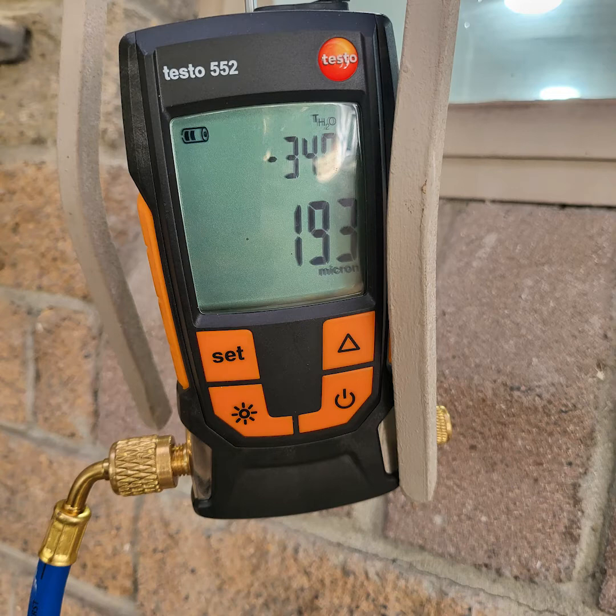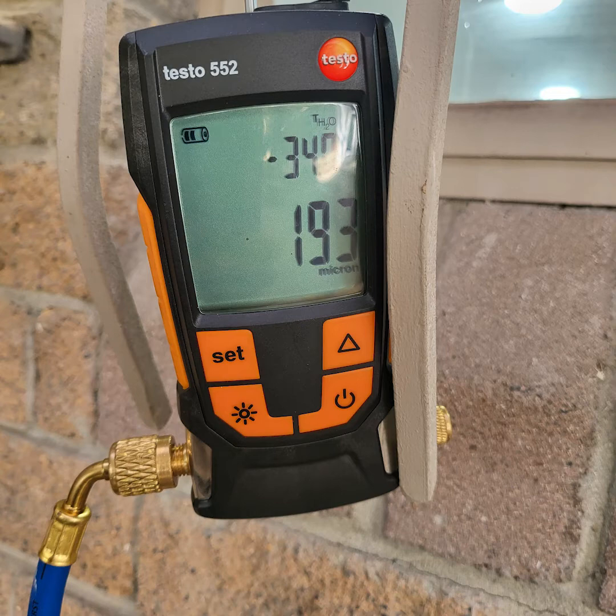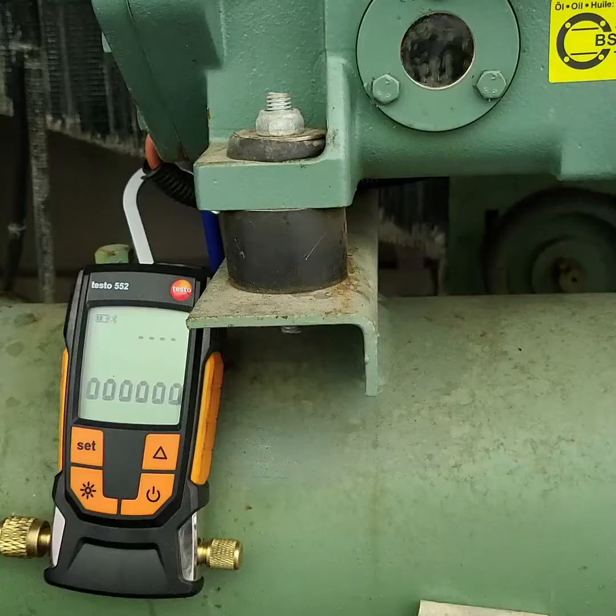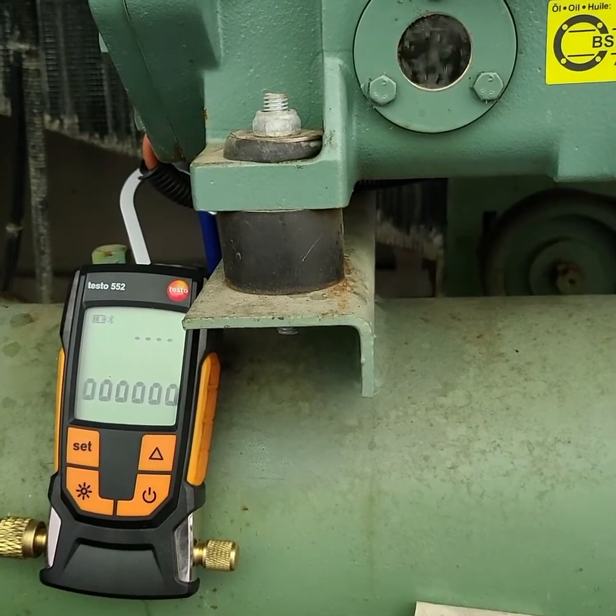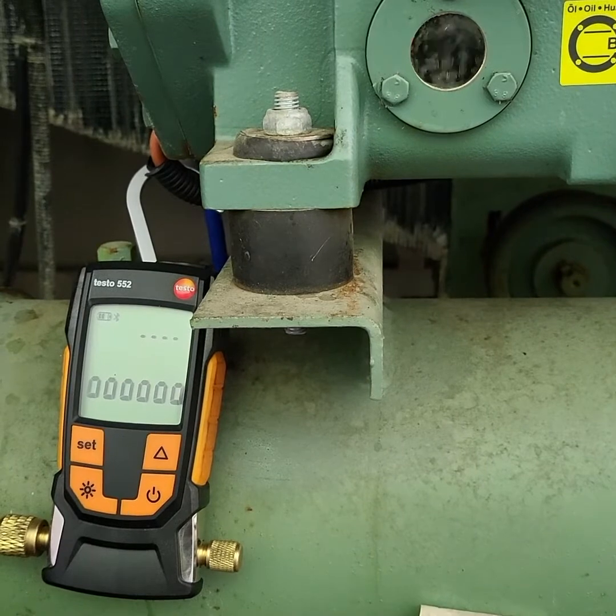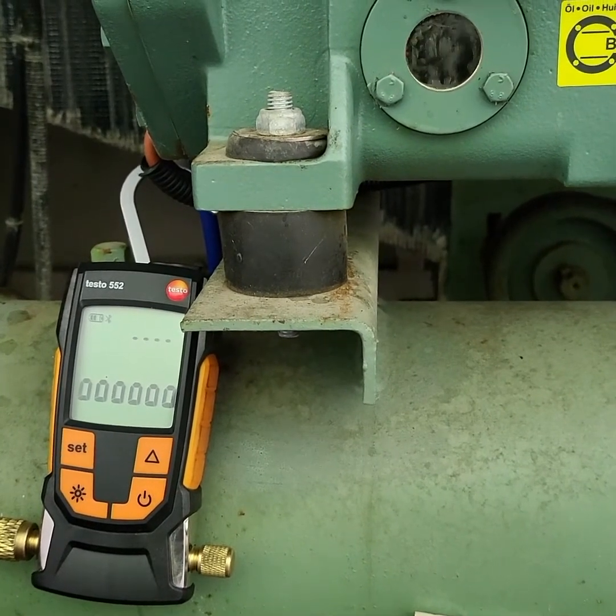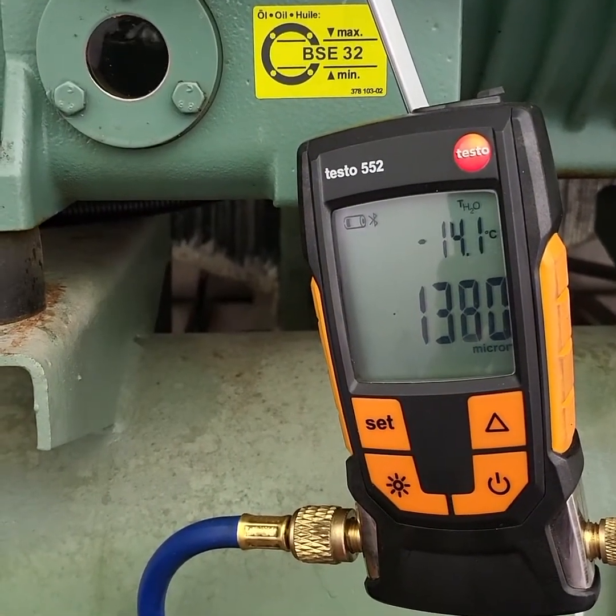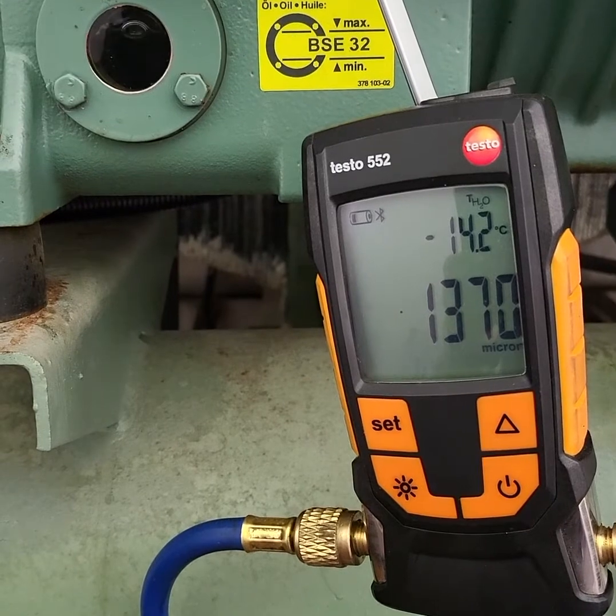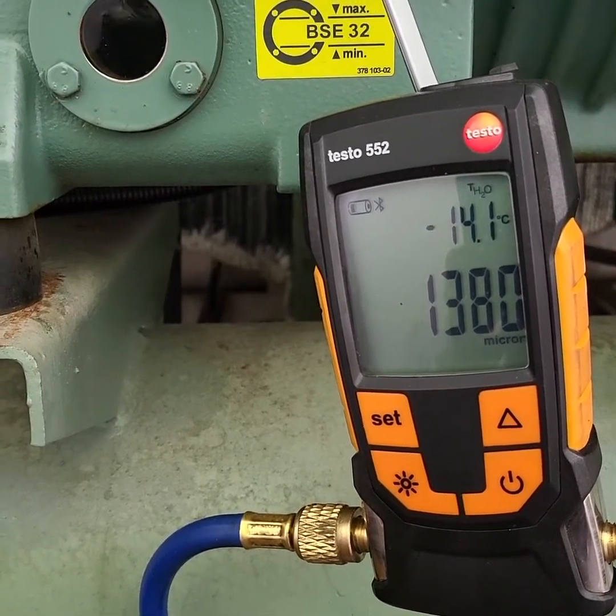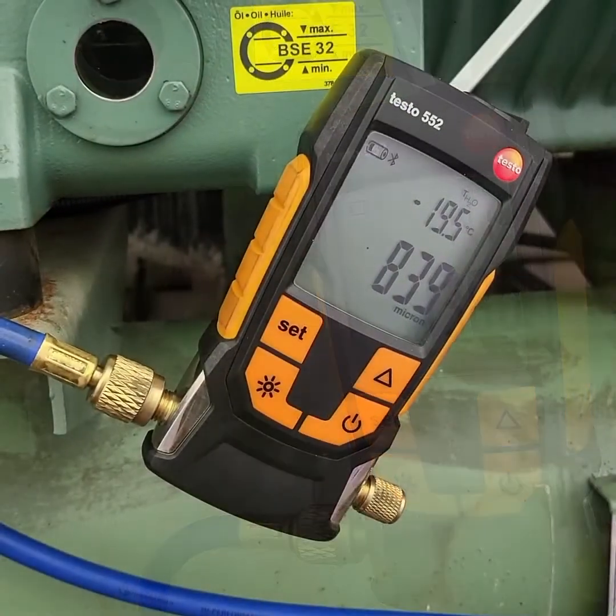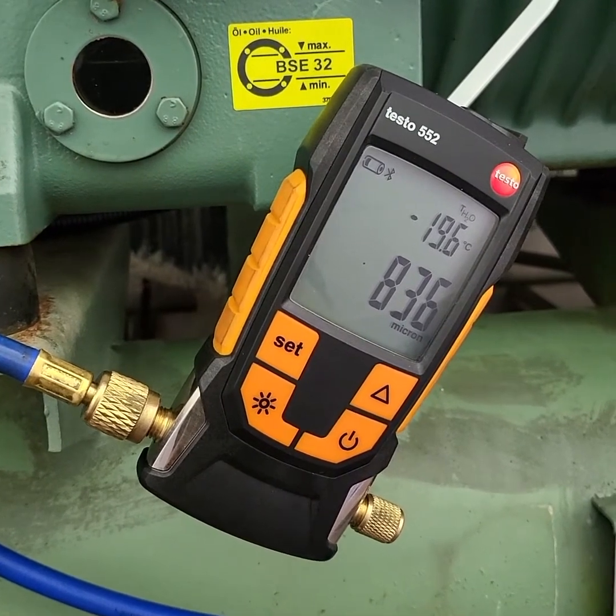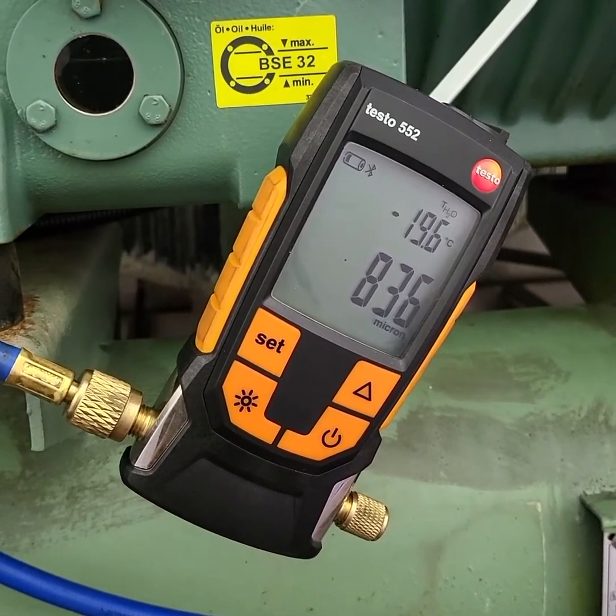Now let's dive into the science behind the secret to the evacuation process. Because a vacuum pump cannot physically remove water from the system, we must first change its state from a liquid to a vapor, which will then allow the vacuum pump to pull the vapor from the system. By lowering the pressure in the system we are effectively lowering the boiling point of any moisture still present, and because that boiling point has dropped well below the current ambient temperature, the moisture will simply boil off. The resulting change of state then allows the vacuum pump to remove that vapor from the system, thereby facilitating the dehydration process.